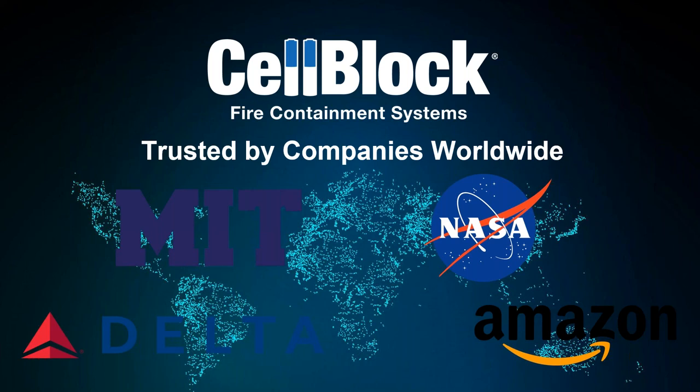Thanks, Travis. And we have another question here from a major city fire department, and that is, for use in an emergency scene, such as an electric car fire, are you developing systems to get the Cellblock onto the source of the fire from a distance, or should fire departments use water to extinguish and then allow the responder to get close enough to pour the Cellblock onto the battery? What are your thoughts? Yeah, that's a really good way to go about it. As far as how you do it in the field, the water will knock down the flames and the heat, which would allow somebody to get closer to put the Cellblock X on it. We have some very large extinguishing pillows that the firefighter can bring in there. So correct, that's a great procedure. You knock the heat signature down, knock the flame down, allow somebody to get close. Once you get that extinguishing pillow on top of it, it's game over. Then it'll put it out.